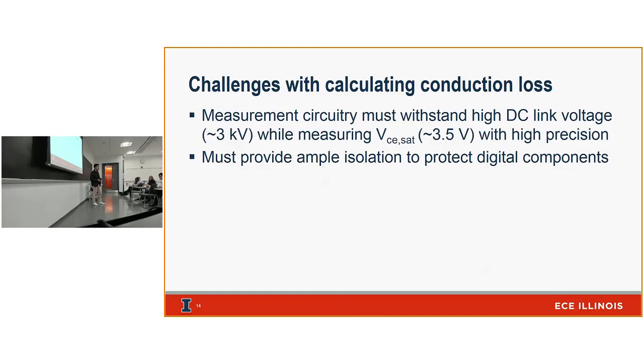The challenge with this is that the measurement circuitry needs to withstand our high DC link voltage while still measuring our on-state voltage with high precision. In our case, our DC link voltage can go all the way up to 3 kilovolts, but our collector emitter saturation drop across our IGBT will typically be around 3.5 volts. So our measurement circuitry must provide enough isolation to protect our digital components. So how do we solve that problem?